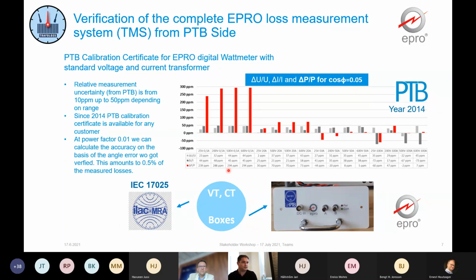By the way, at the very well-known 0.01 power factor, we can only estimate accuracy on the basis of the angle error we got verified from the PTB. We state in our accuracy table that it is 0.5% of the measuring value at 0.01 power factor and 60 Hz.